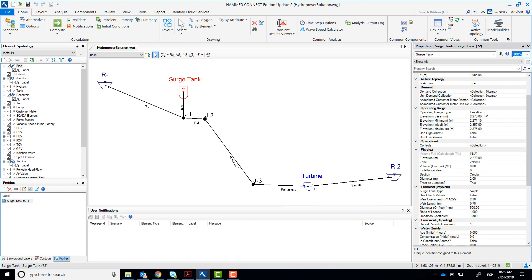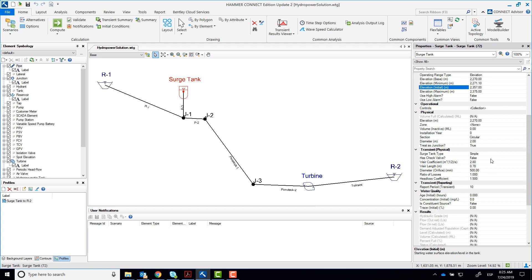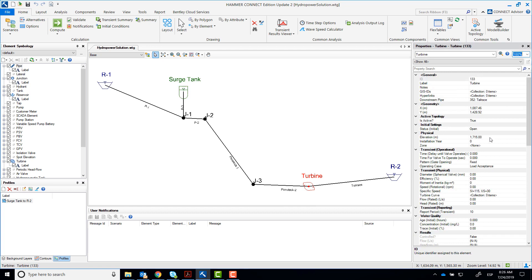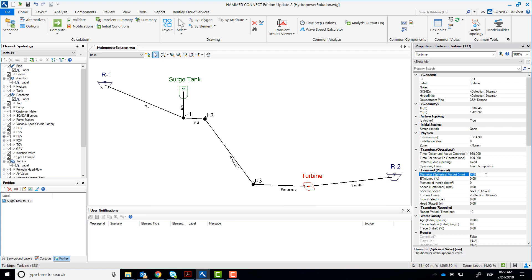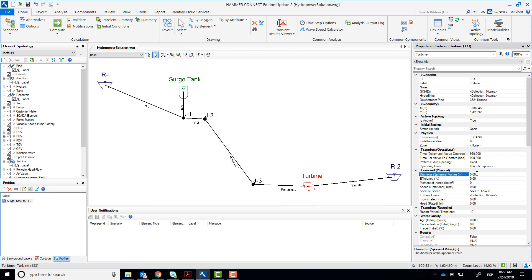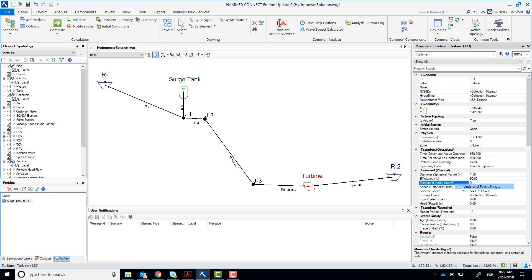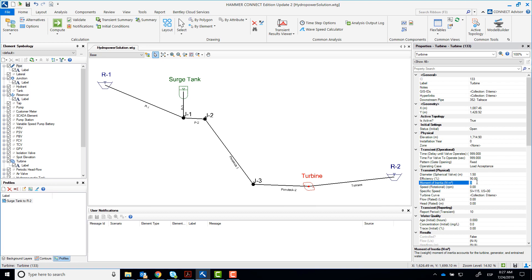We'll now enter some missing information for the surge tank. We'll also be entering data for the turbine. Remember that we will not be operating the spherical valve during the simulation, which is only 150 seconds. We'll set the time to 999 seconds to make sure that this valve remains open during the simulation. We'll be changing the turbine's operating case for each of the scenarios. But what will be common in all scenarios is the physical properties of this turbine, like diameter, efficiency, moment of inertia, et cetera. Type the information that you have been provided in the workshop for these fields.